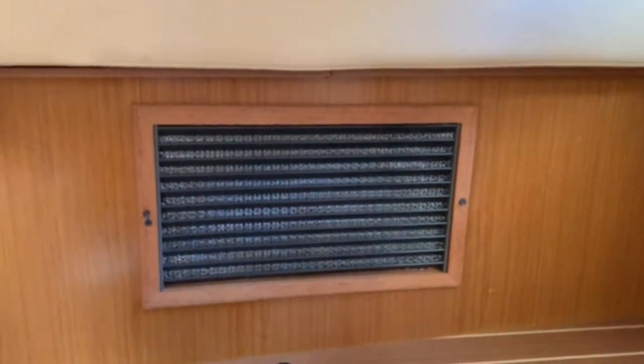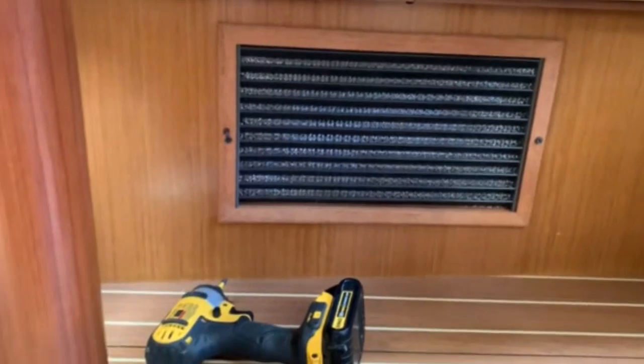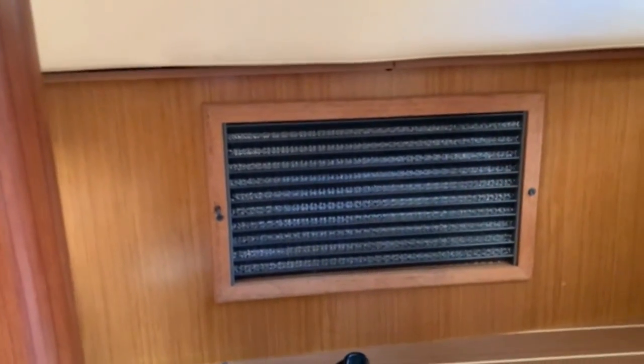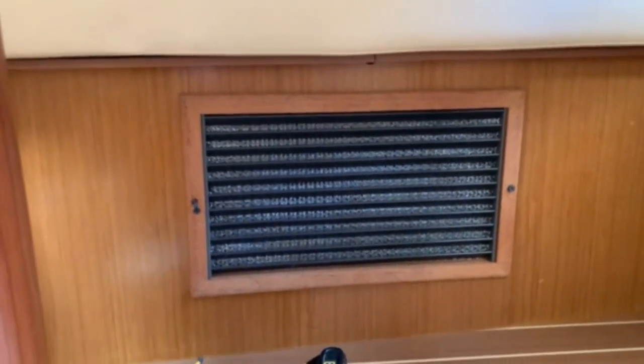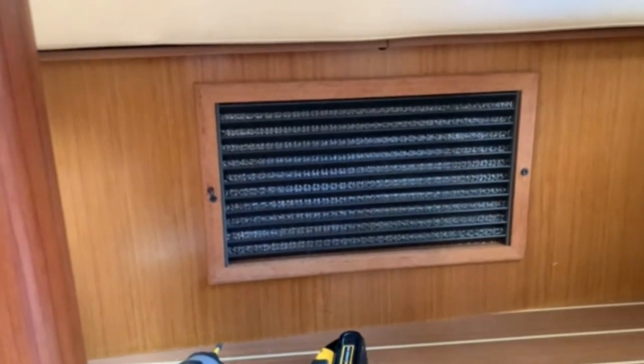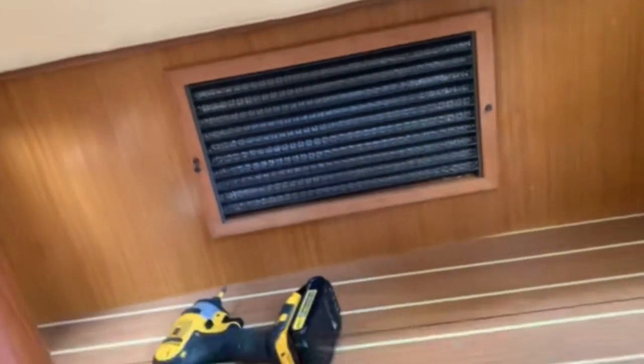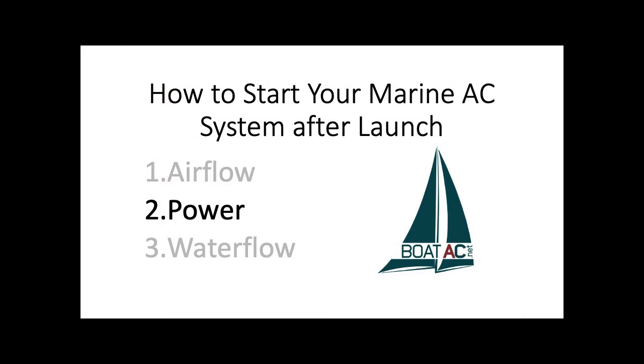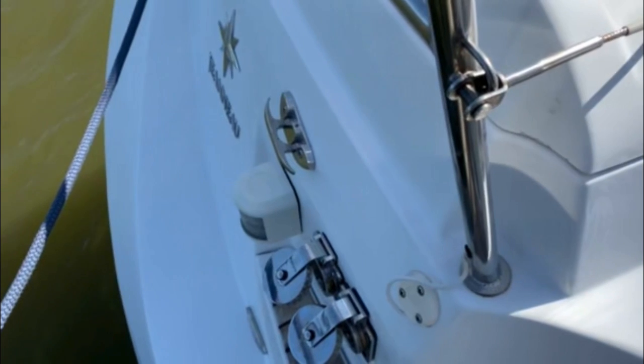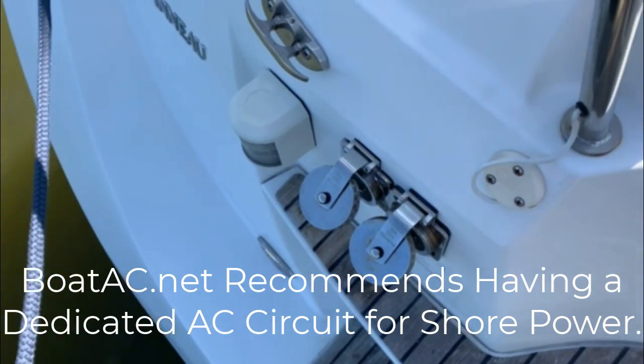If these things get clogged up, air isn't getting sucked through and into the unit, and it basically starts freezing up the coil. If the filter is clogged, it'll cause the unit to freeze up because it's not getting enough air.